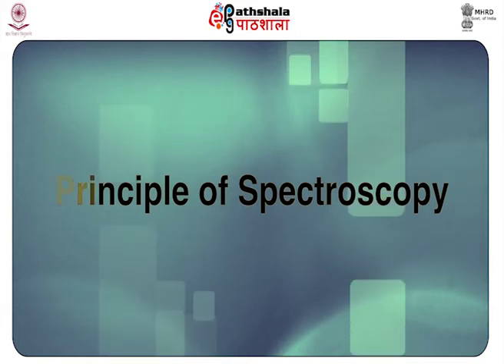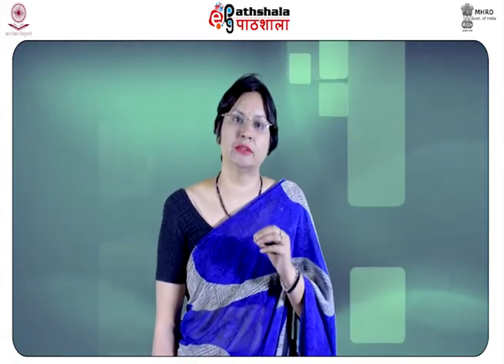If we look at the principle of spectroscopy, although there are a number of spectroscopic techniques, each based on a different basic principle, a typical spectrophotometer is said to consist of a light source that provides light of a known wavelength, a holder to position the sample, which may be solid, liquid or gaseous, and a system of lenses and photocells that compare the light shining on the sample with the light passing through. That difference is compared and finally put up on the plot as the spectrum.